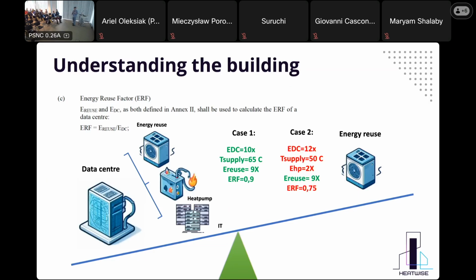Amazing. But what happens if I have a data center which consumes the same, but it can only give back 50 degrees, and 50 degrees is not acceptable for my building, maybe because of bacteria issues when I want to supply it into the system. Then I had to add one heat pump, and the heat pump consumes 2x, which in total increases my data center's consumption. The cooling system is working fine, the IT is working fine, but the building has some restrictions with heat demand. Then what happens? Our ERF dropped to 0.75.